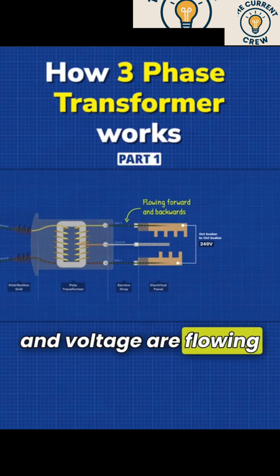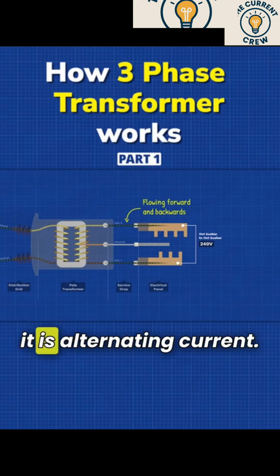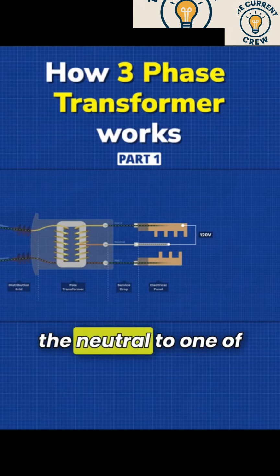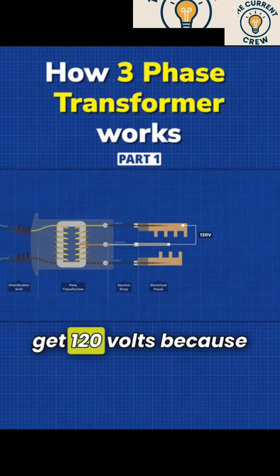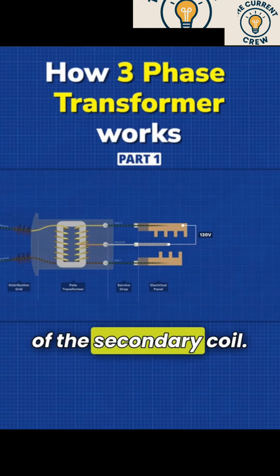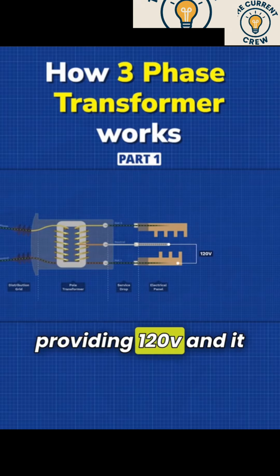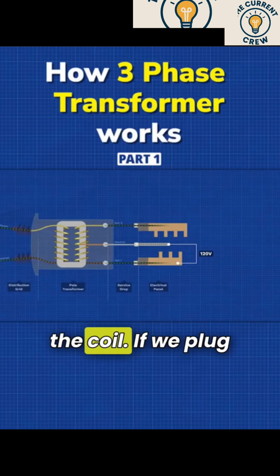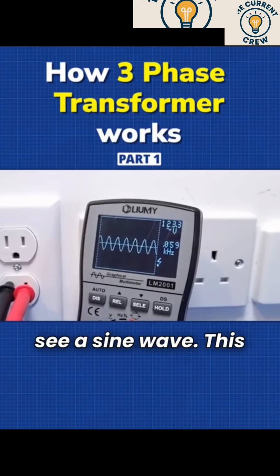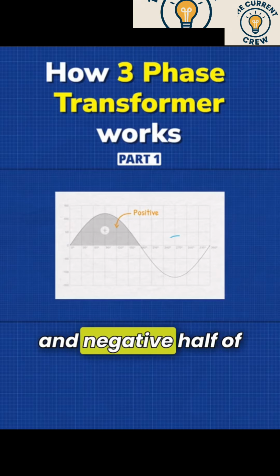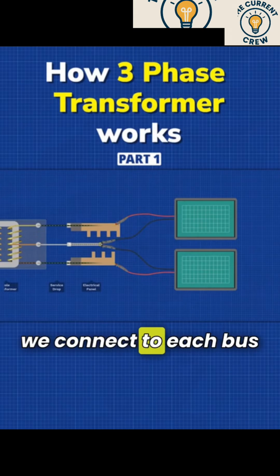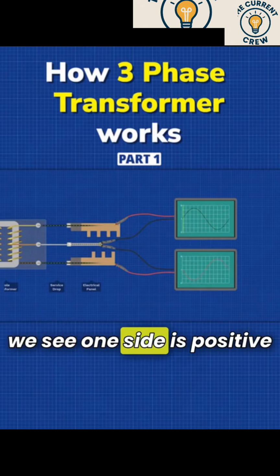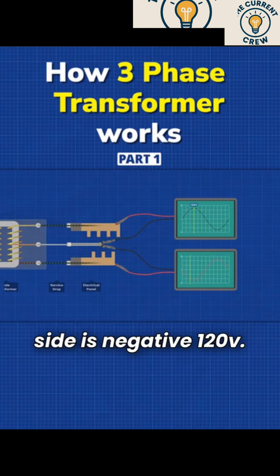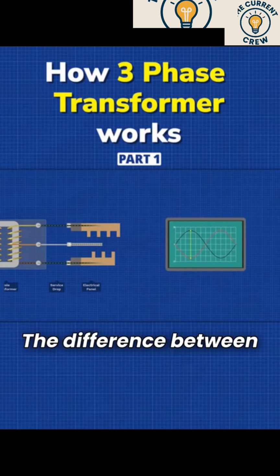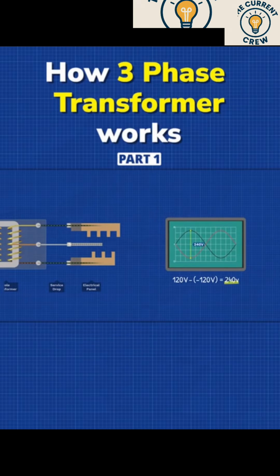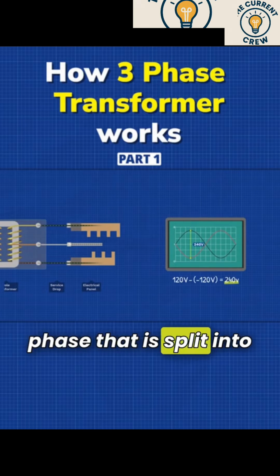The current and voltage are flowing forwards and backwards between these two as it is alternating current. But if we connect from the neutral to one of the hot bus bars, we get 120 volts because we're using just half of the secondary coil. The other side is also providing 120 volts, and it uses the other half of the coil. If we plug an oscilloscope into the outlet, we would see a sine wave. This sine wave has a positive and negative half of the AC sine wave. If we connect to each bus bar and the neutral, we see one side is positive 120 volts, while the other side is negative 120 volts. The difference between these gives us 240 volts. So this is just a single phase that is split into 2.